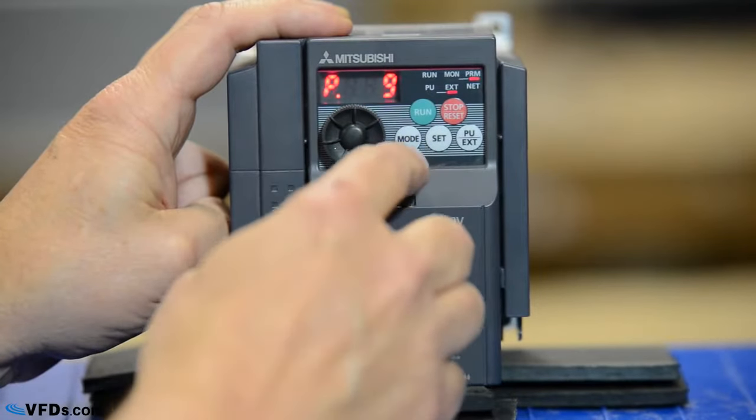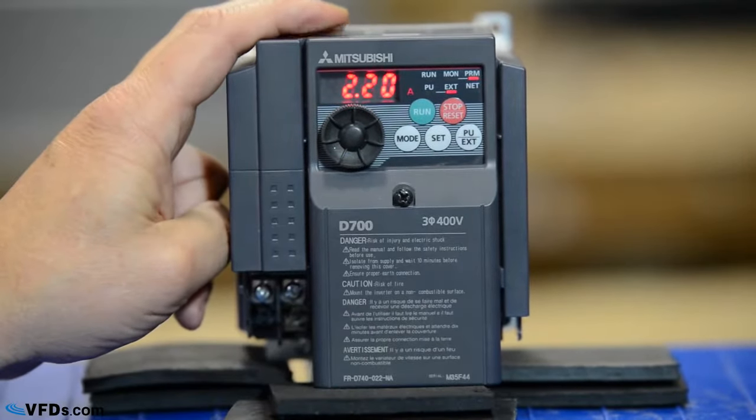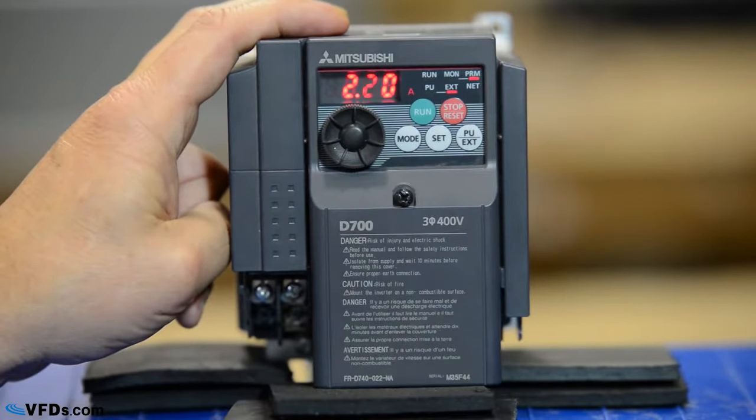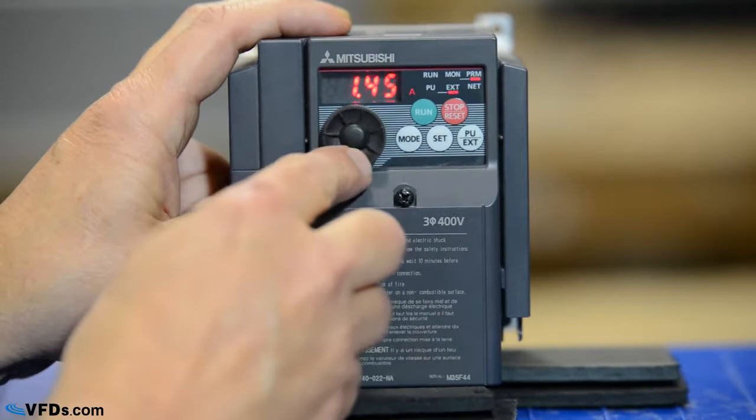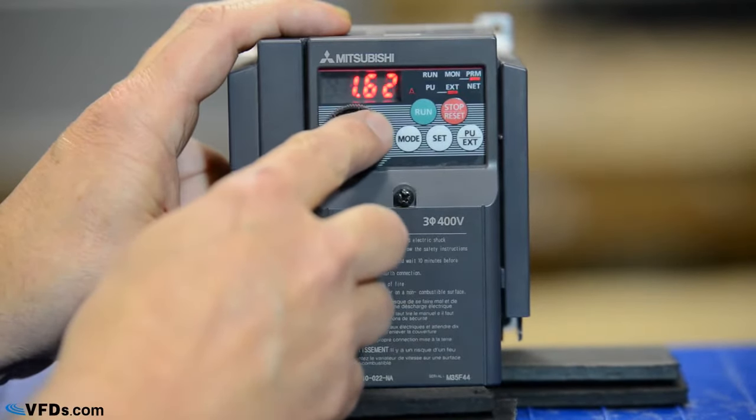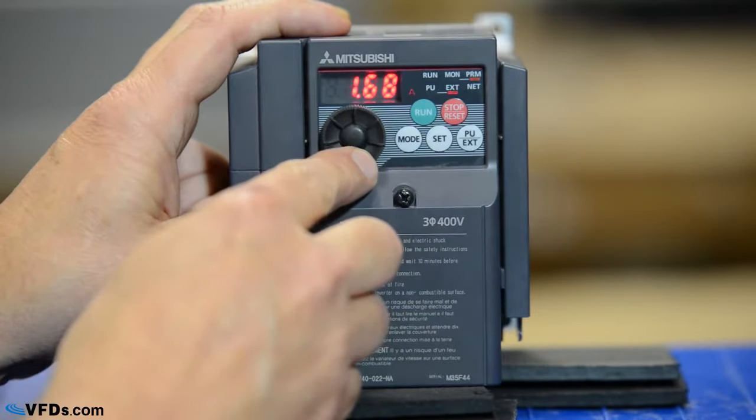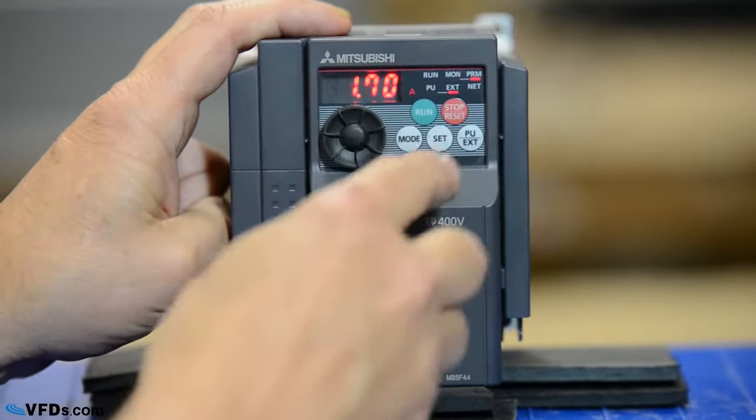Finally, parameter 9 is my motor nameplate amperage. My motor full load amps on this motor is 1.7 amps, so I'll simply change that down here to 1.7 amps, knowing that the drive will now be able to protect my motor from overloads.